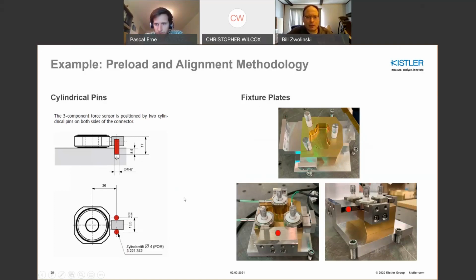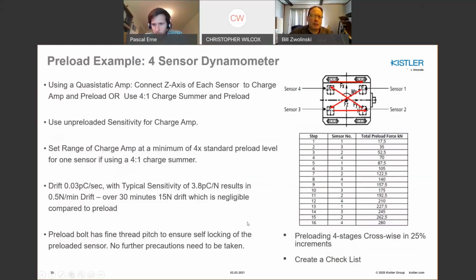you can always consult us at the factory. In terms of preloading, it's like changing the tire of your car. Really the way you do it is you don't want to torque down any one sensor to the maximum limit and then go to the next one. That wouldn't be the right approach. You want to use, say, a crossing pattern or star pattern approach, and basically you go to a 25% standard. So if you have a full preload requirement of 100%, you take 25% increments and repeat it 4 times. In this way, you get even load distribution, and you get a good preloading methodology.